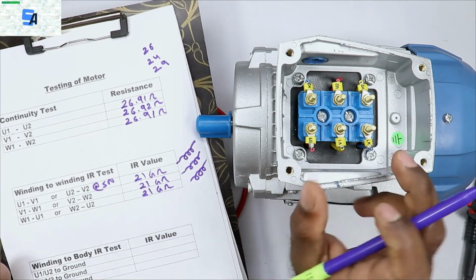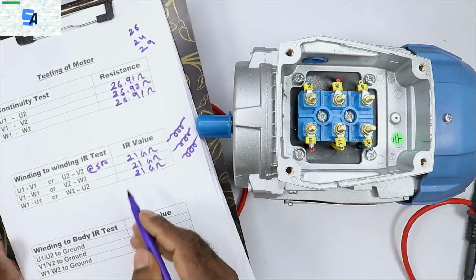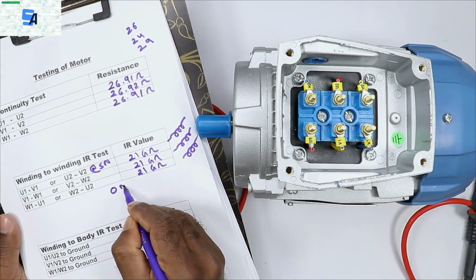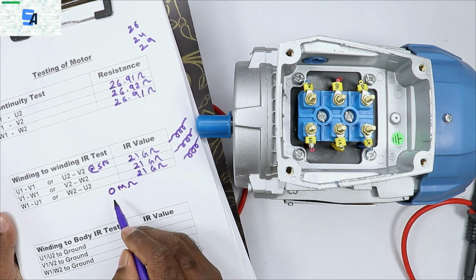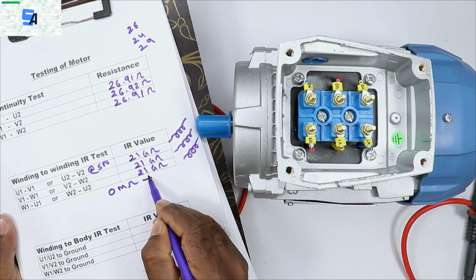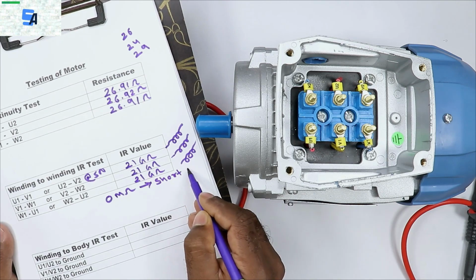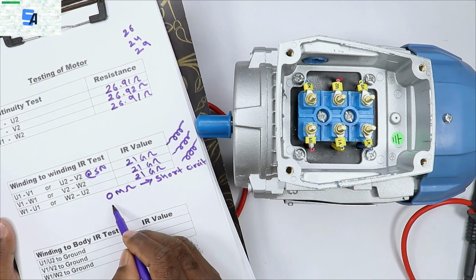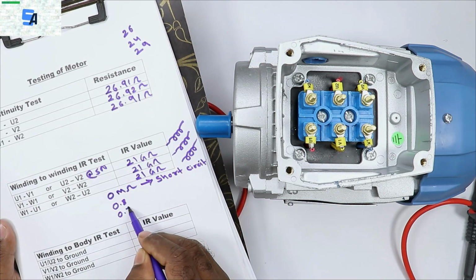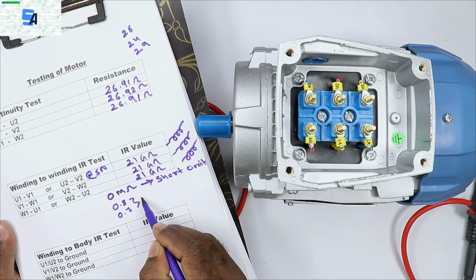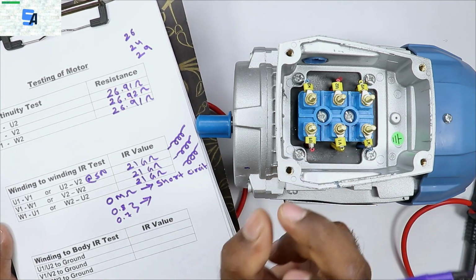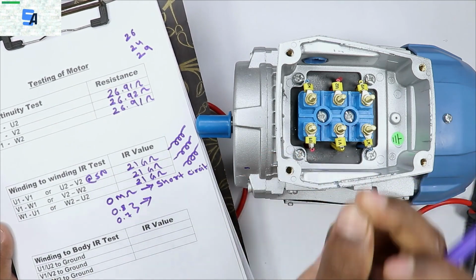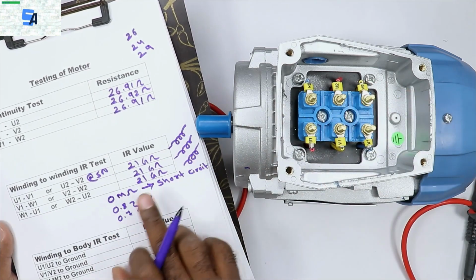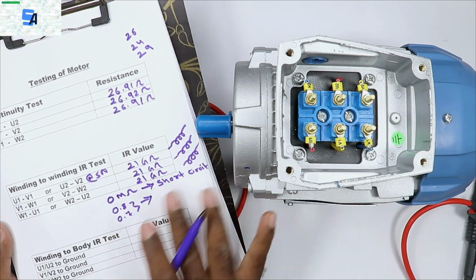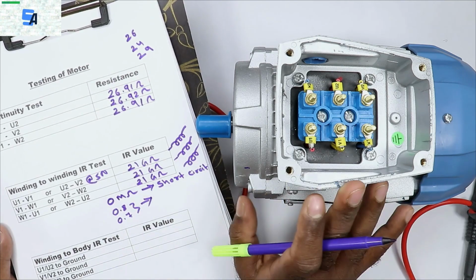Look, if at the time of measuring you get a value of 0 mega ohm, it means the winding of this motor got short circuited. Besides, if you get values like 0.8 or 0.7, then you can say the insulation of the winding got weak and soon the windings are going to short circuit with each other. It means if you get a value less than 1 mega ohm, then the motor needs to be checked.